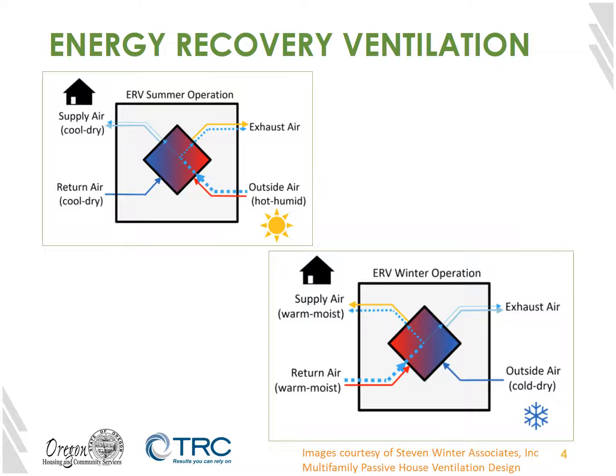For most of the Northwest, an ERV or energy recovery ventilator is not necessary or even recommended. In rare cases where buildings are located in high moisture marine climates, for instance in a rain shadow, in a deep valley, or areas protected by mountainous terrain, an ERV in the summer can reduce the amount of moisture in the outside air that is delivered to the inside of the building. Heat and moisture are transferred to the exhaust airstream, reducing both the cooling and dehumidification loads of the building associated with ventilation.